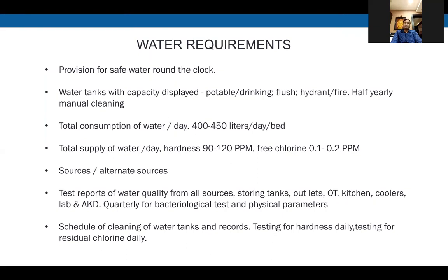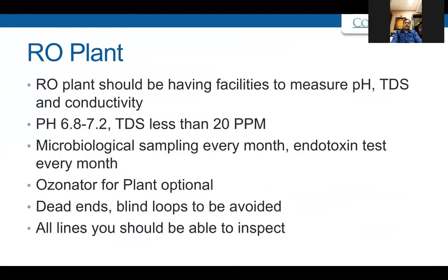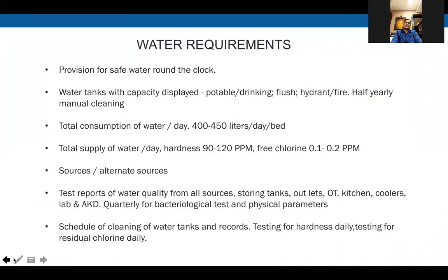So the prescribed testing is generally quarterly for biological testing, monthly for endotoxin tests, and also physical parameters of the water. For example, hardness, as I have already said, plus any other chloramines, etc. All those aspects need to be checked at least quarterly. The schedule of cleaning of water tanks also must be prescribed. As prescribed by NABH, it is six monthly, but it can be more frequent in case there is a requirement of water tanks to be cleaned.